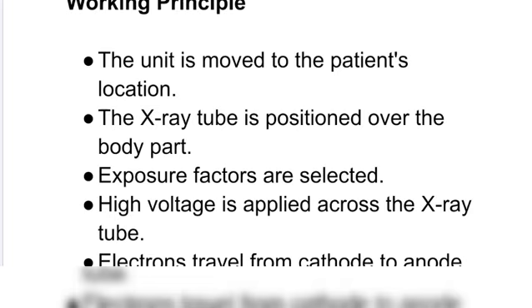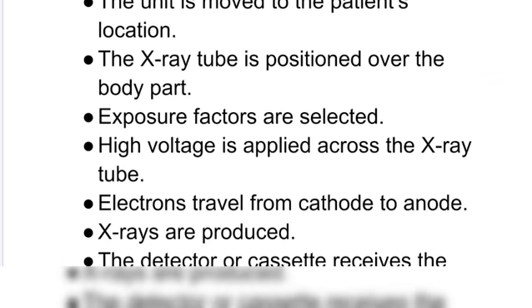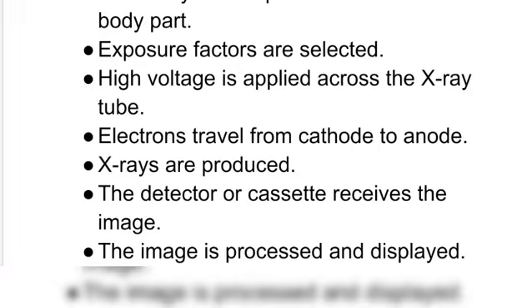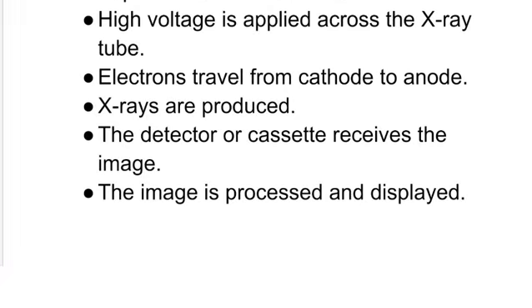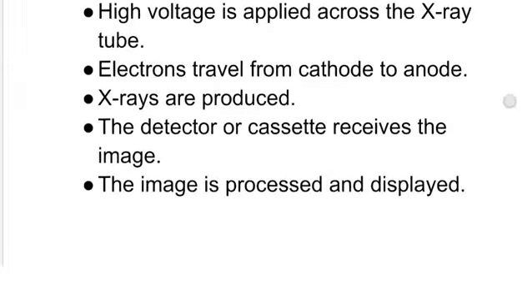What is the working principle? This mobile X-ray unit can be moved to the patient's location, and the X-ray tube is positioned over the body part of the patient. The exposure factors are selected, and a high voltage is applied across the X-ray tube. When the high voltage is applied, the electrons travel from the cathode to the anode, and the X-rays are produced. The detector or the cassette receives the image, which is further processed and displayed on the monitor screen, where we take the radiographs of the particular part of the patient.